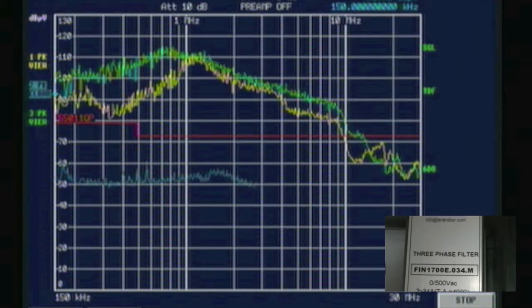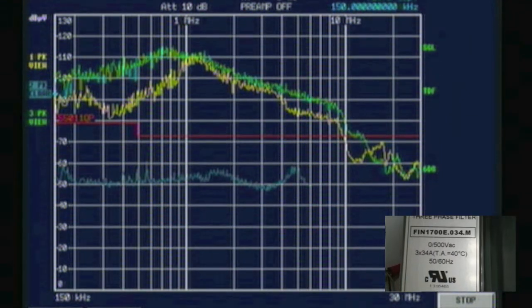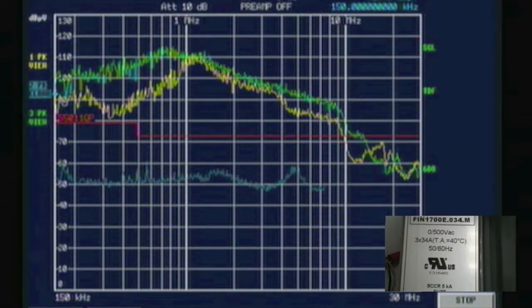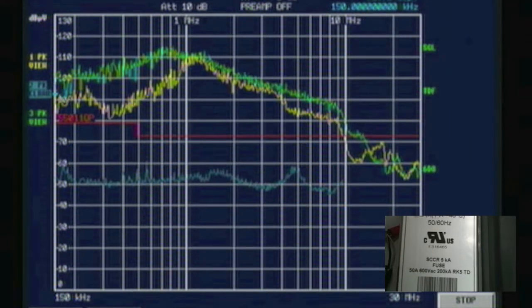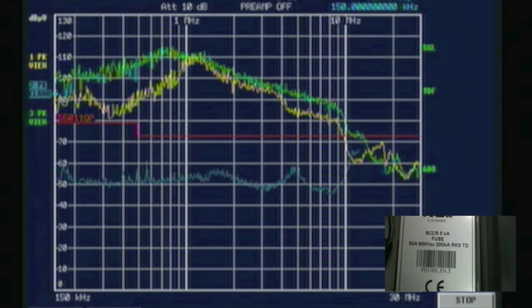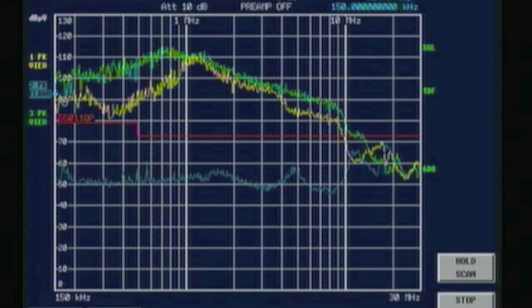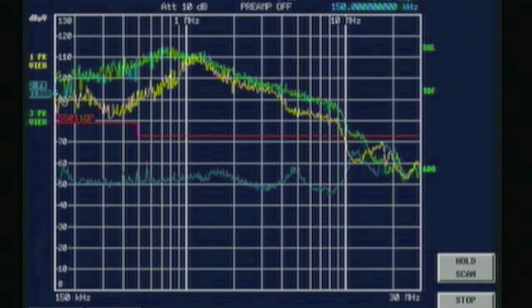This graph line in blue measures the electrical noise generated by an AC drive with the addition of an Enerdoor filter. The EMI filter works in frequency ranges from 150 kHz to 30 MHz, reducing the noise generated by today's AC drives to below the European and FCC limits.